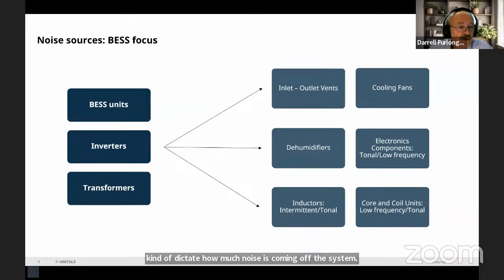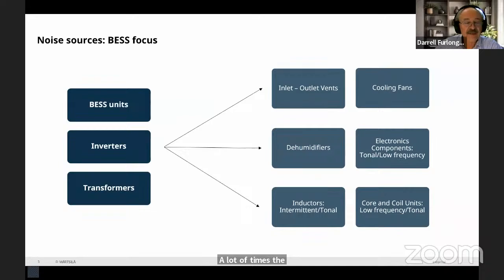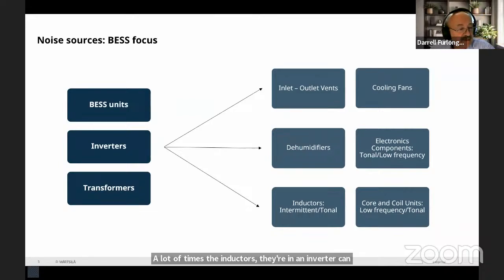Dehumidifiers also have noise. In the inverters you also have components that can vibrate, which we call tonal low frequency noise. A lot of times the inductors in an inverter can start to vibrate, usually at a harmonic of the frequency the utility is running at. So if it's 50 hertz for European systems, a 100 hertz tone can come off the equipment.